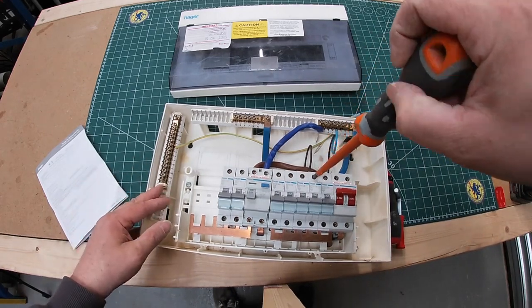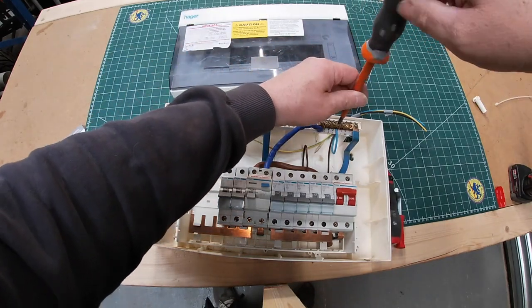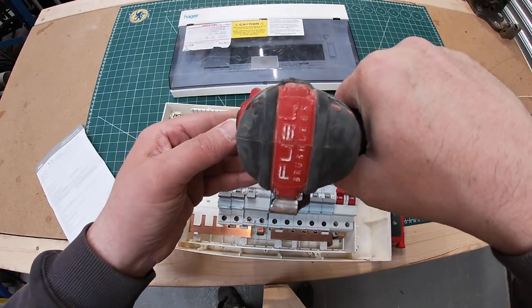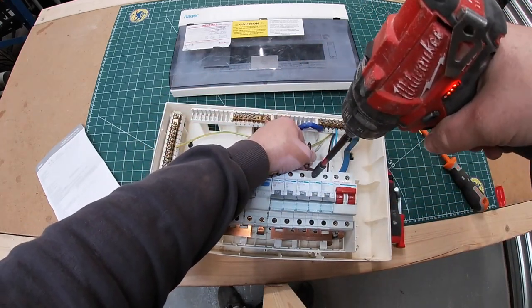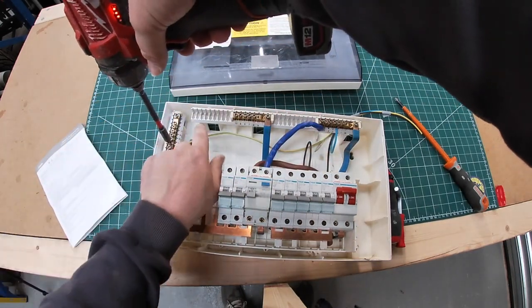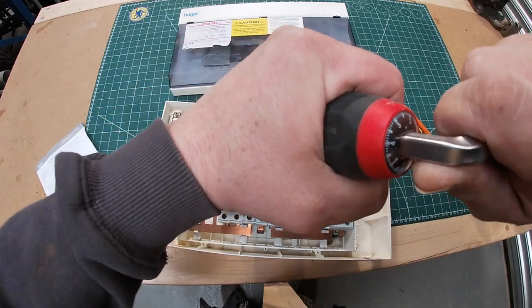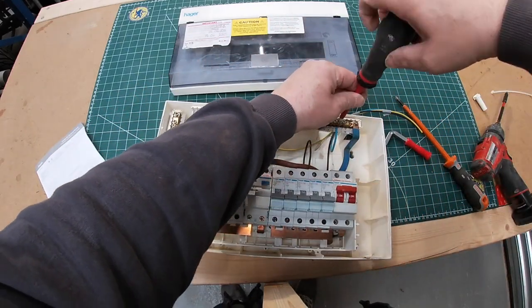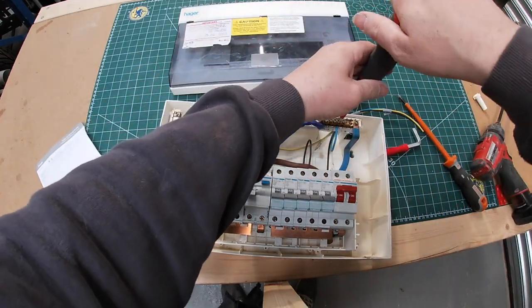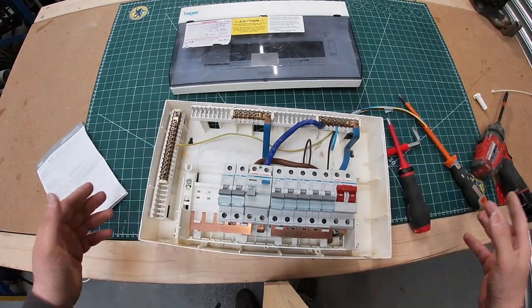And then this one is even more, and I think the maximum for an MCB is 2.8. So bringing that down to 2.8 - that was about spot on the live. Just a quick example of what we're doing - I noticed I was over-tightening, so I don't know if that shines any light, it's a bit of a shitty experiment, but I hope it just highlights something. It's the same with the old battery drills. See, I've got this long drill bit - what I like about this is that the drill doesn't actually block your vision. I obviously know this is going to be too tight. So I'll change that to 1.5 - straight away too much. I'll bang that straight up to 3 - yeah, that was just probably bang on 3. Just saying, be aware of it.